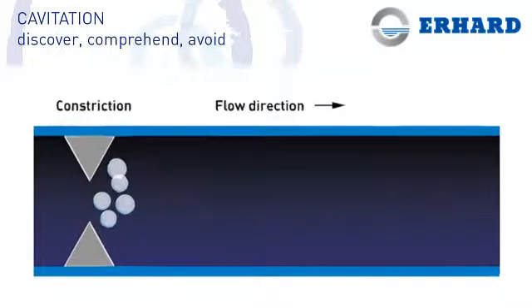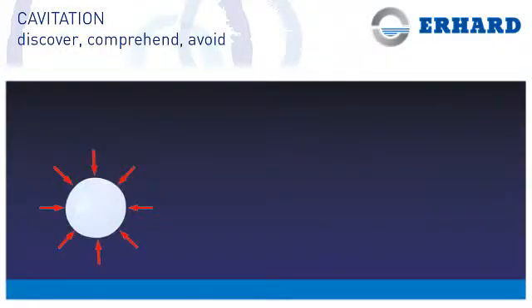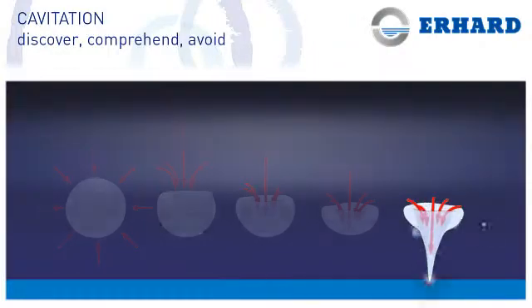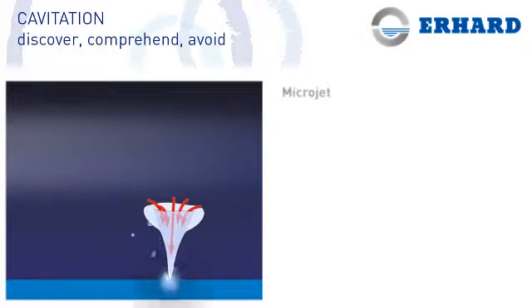In the case of cavitation, the vapour bubbles which form due to a pressure drop implode, recondensing to their liquid state when the pressure rises. The water surrounding the vapour bubbles is accelerated inwards within fractions of a second. Several of the resulting microjets hit the body or pipe wall at very high speed, which causes pressure peaks up to 10,000 bar.